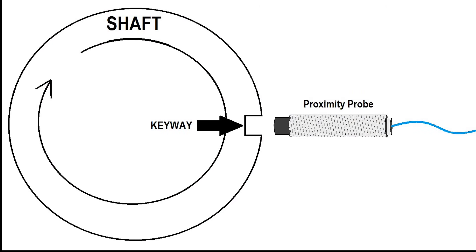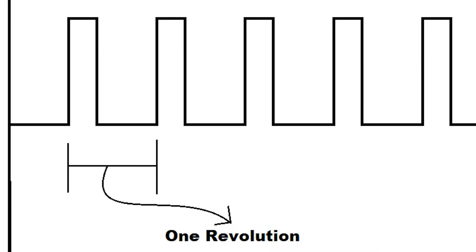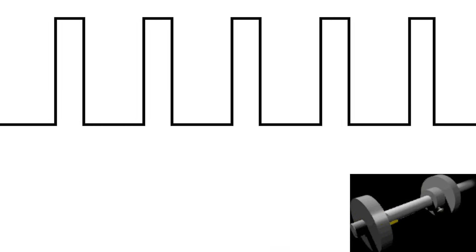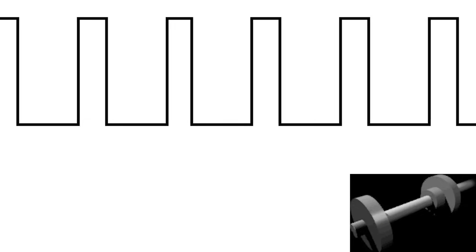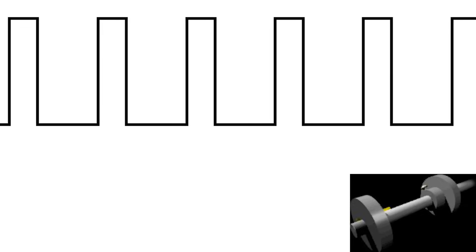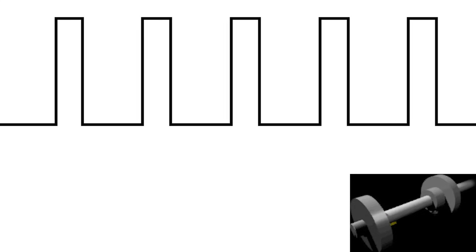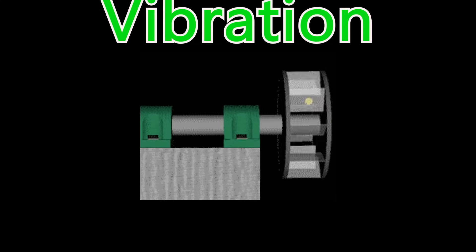A proximity probe can be installed over a notched section of a rotating object such as a keyway. Each time the keyway passes the proximity sensor, a change in voltage occurs representing one revolution. By applying a time factor to the voltage spikes, an equipment RPM can be measured. This type of measurement is referred to as a Keyphasor.